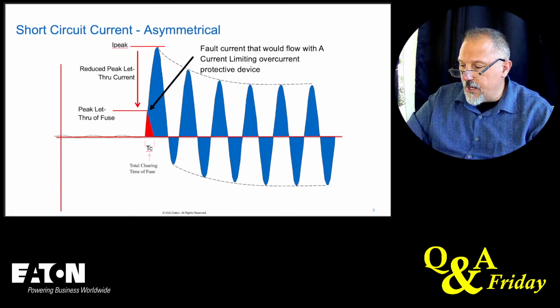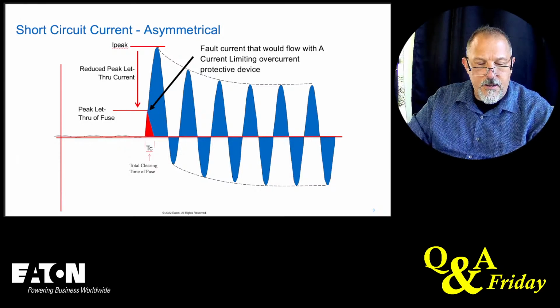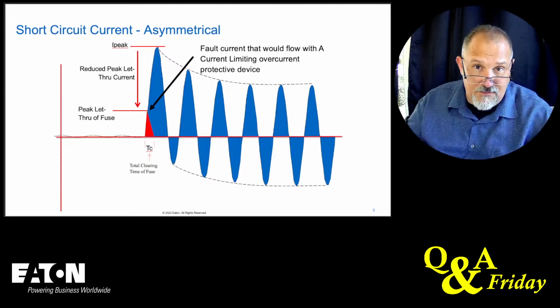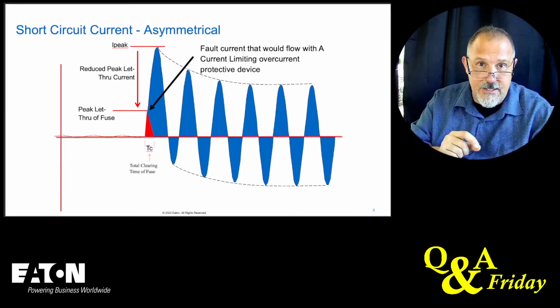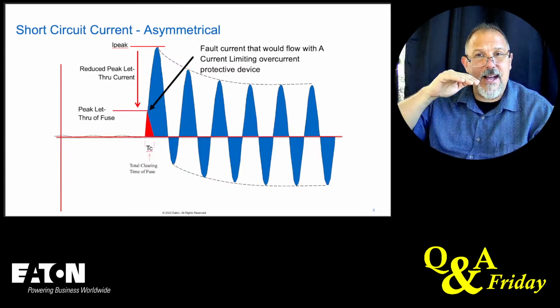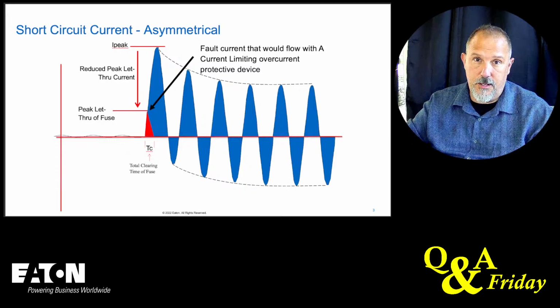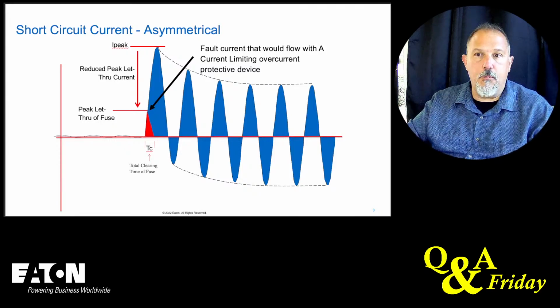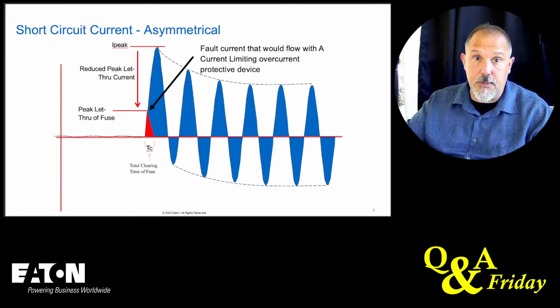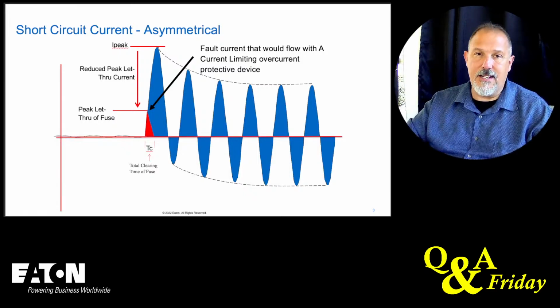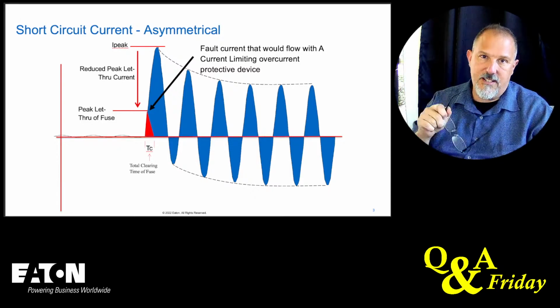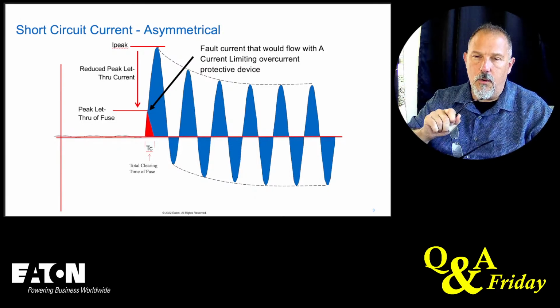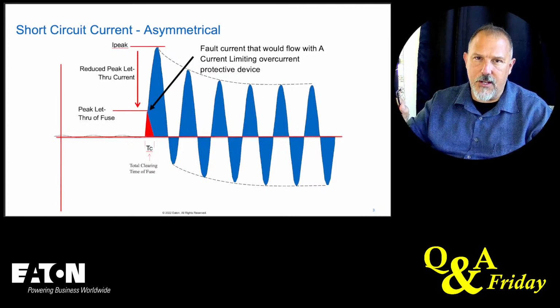And then 1/4 cycle, which is right there at that peak, that is 0.00415 of a second. That's an important thing to remember from a time perspective, because as we look at trip curves, if my trip curve has a clearing time of 0.1 seconds, is it current limiting? Can it possibly be current limiting? If that trip curve in its instantaneous region is going to take 0.1 seconds to clear, when we know that current limiting devices have to clear within a half cycle, which is 0.0083 seconds. If my overcurrent device takes 0.1 seconds, it can't be current limiting, right?